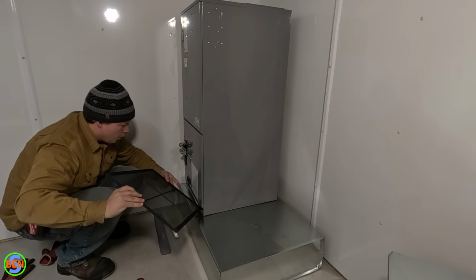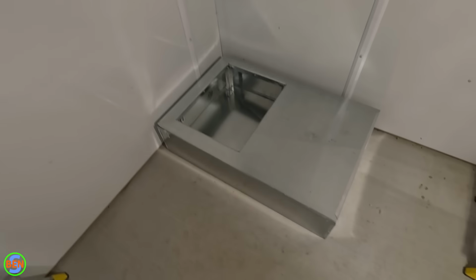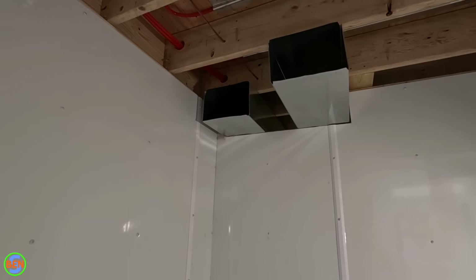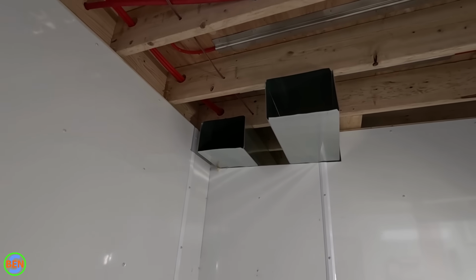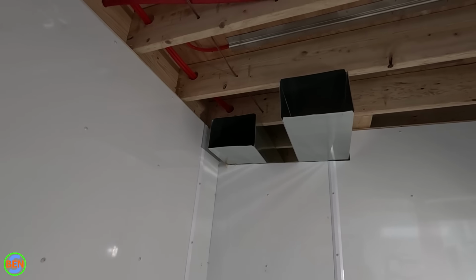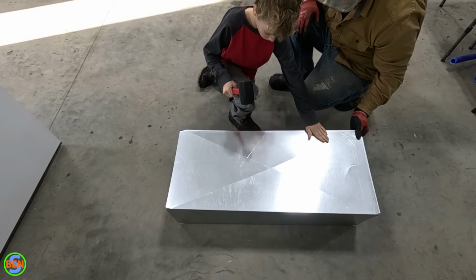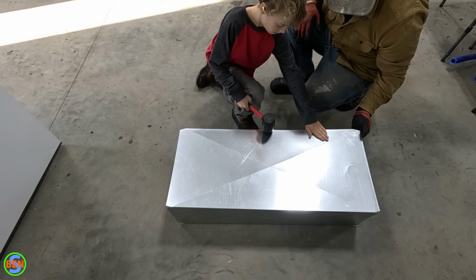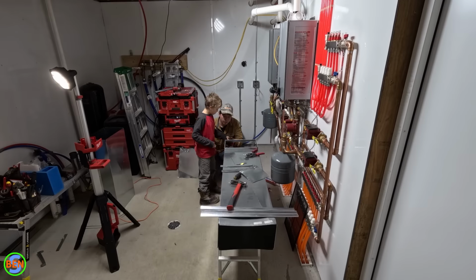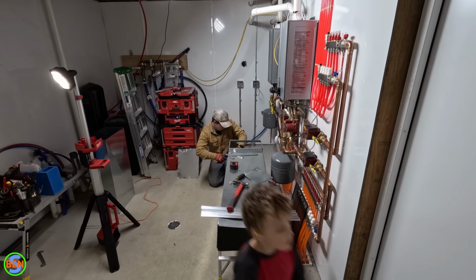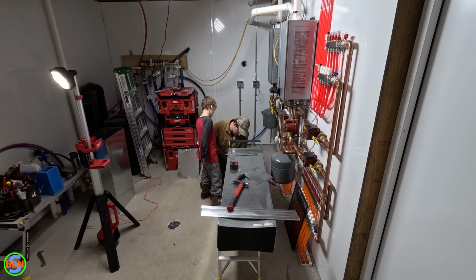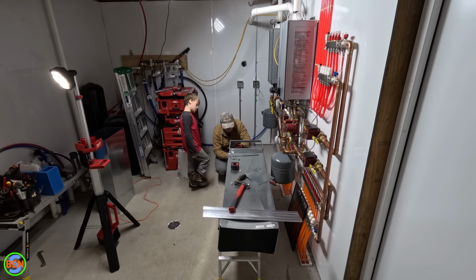Now, we sized up the ductwork, and I've talked about ductwork sizing, so I'm not going to go into too much detail here, but we have a supply and a return that is large enough to handle that 800 CFM of airflow that's needed for a 2-ton inside unit. And for those of you who don't know already, 24,000 BTUs is equal to 2 ton. So it comes out to be that 1 ton of cooling is 12,000 BTUs.